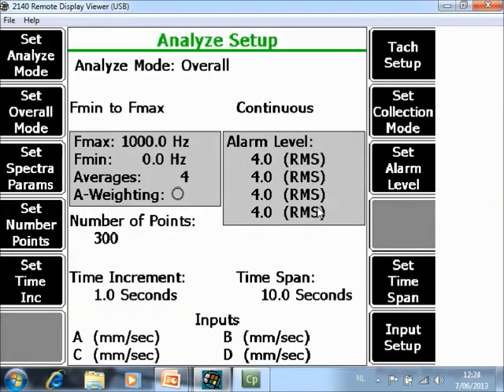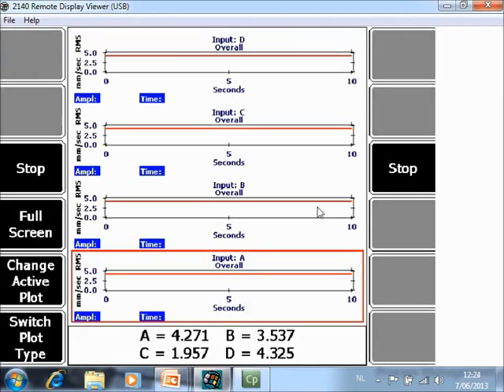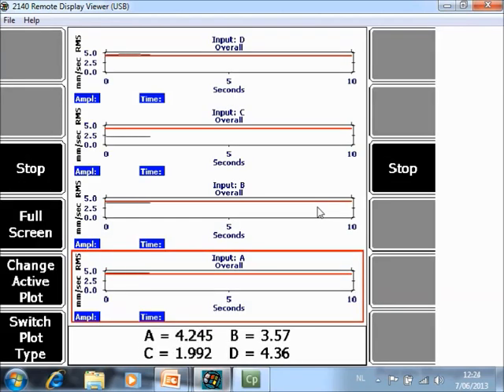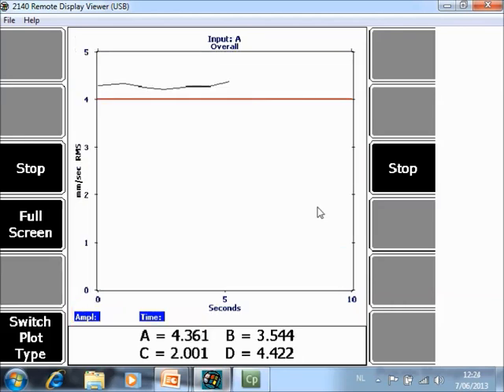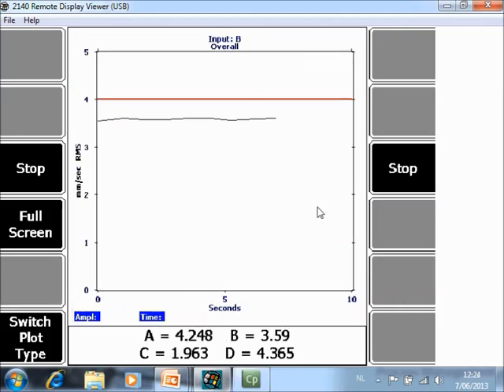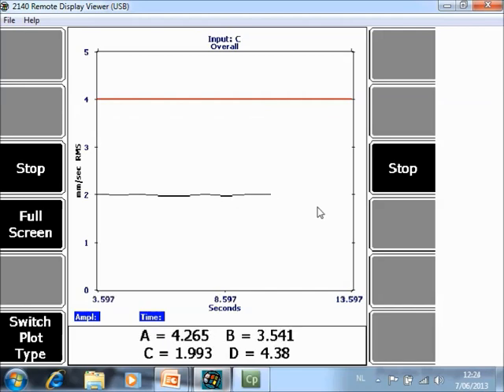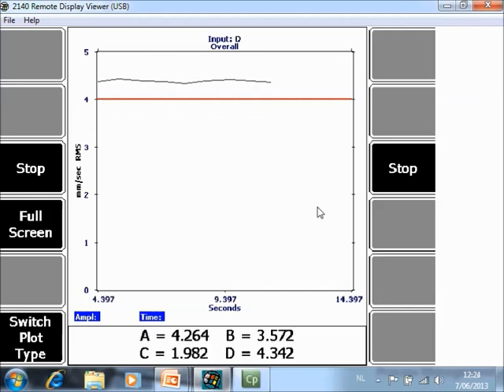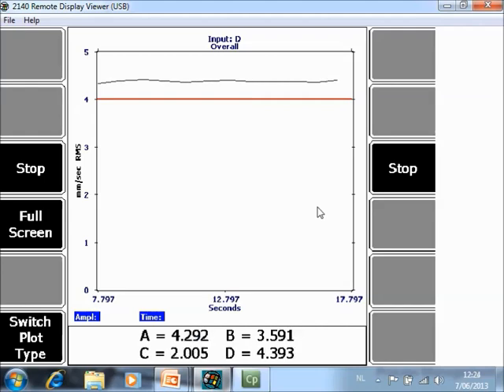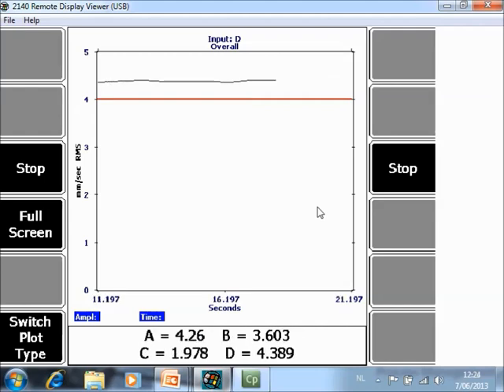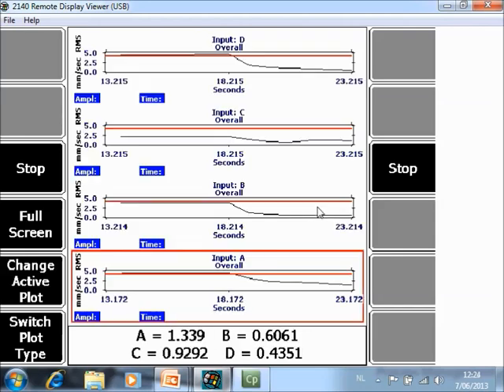Now I collect data again. And now you see for certain channels we are below alarm and for certain channels we are above alarm. Now if I switch off the motor, so I measure the shutdown, you will see the result of the overall value immediately.